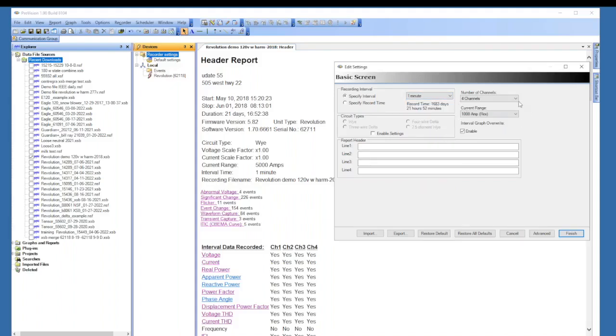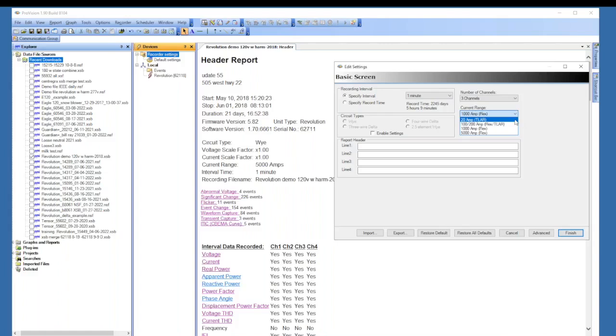Then you have the number of channels. If you're not recording 4 channels, you go 3 channels. It will also increase your record time. And then you have your current ranges. So if you're using TLARs, you have a 20 amp current range and a 200 amp current range. At 20 amps, if the TLARs don't see anything over 10 amps, it will cycle down and you'll see 10 amps on your header report. So whatever you selected here will also be reflected on your header report.